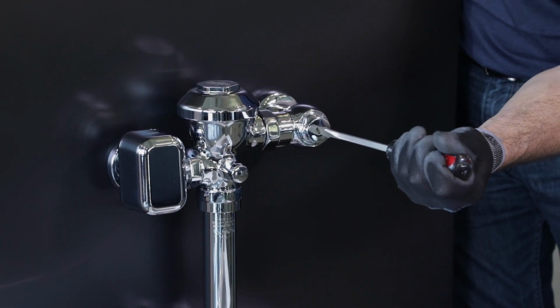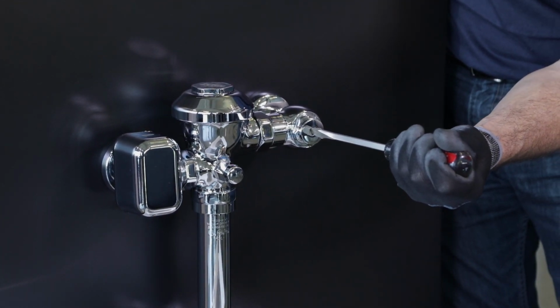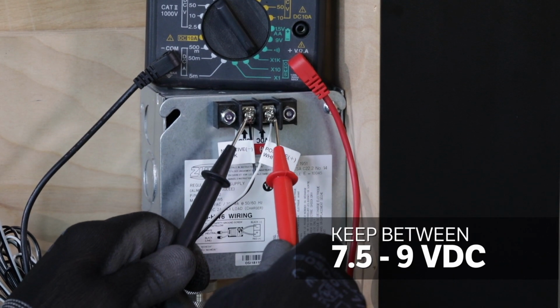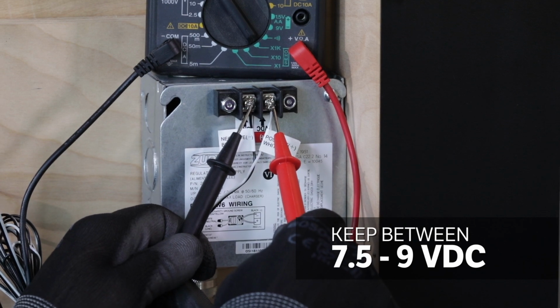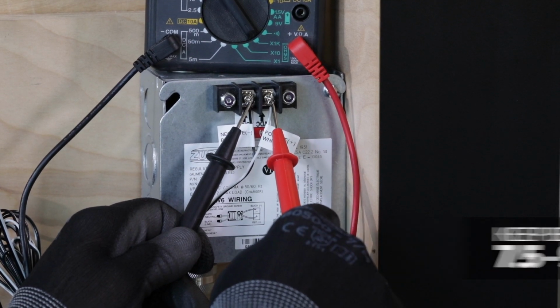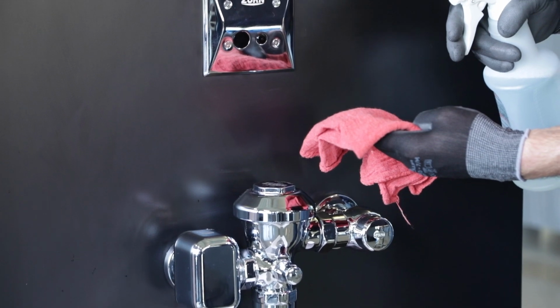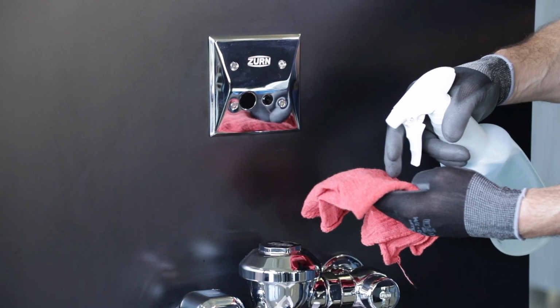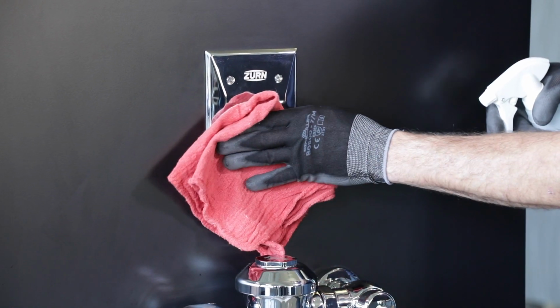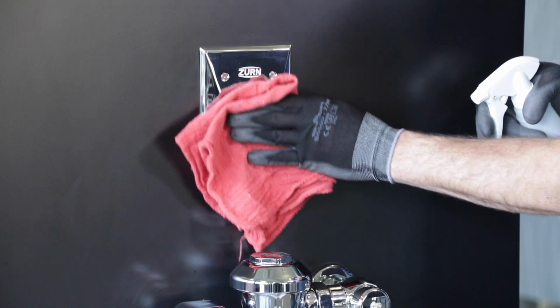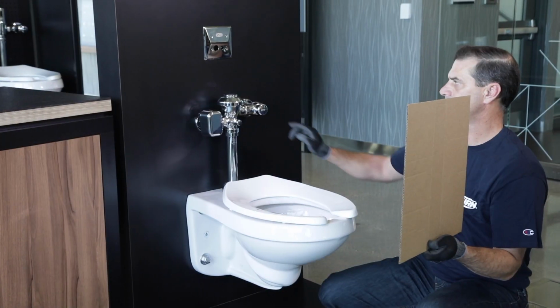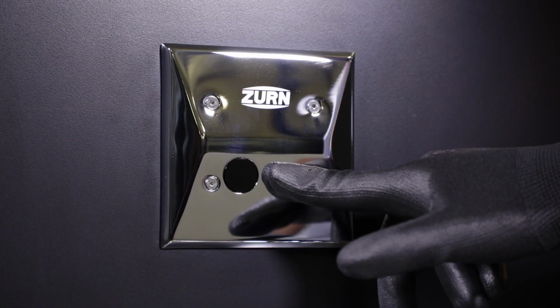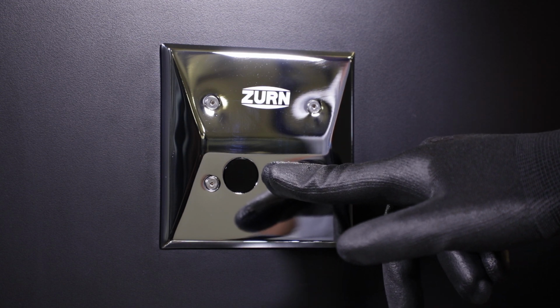If that doesn't do the trick, confirm that you have adequate water supply. Next option, verify the power supply output voltage is between 7.5 and 9 volts DC, which we outlined in problem 1. The 4th cause to examine is a dirty sensor lens. Clean the lens with mild soapy water and a soft cloth. Also, make sure the sensor isn't picking up a reflective object, like a mirror or stainless steel material. If none of these pan out, recalibrate the sensor, which we covered during problem 1.